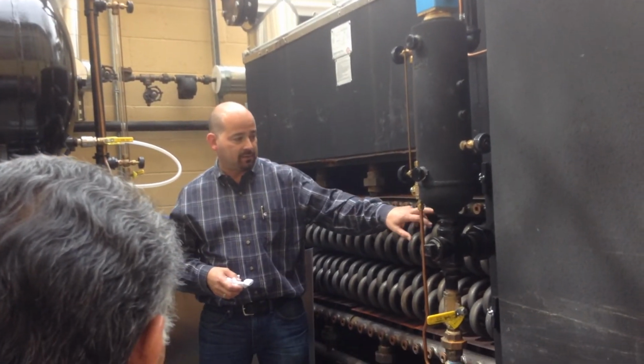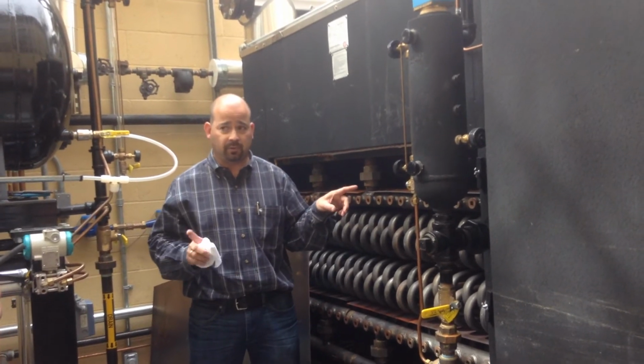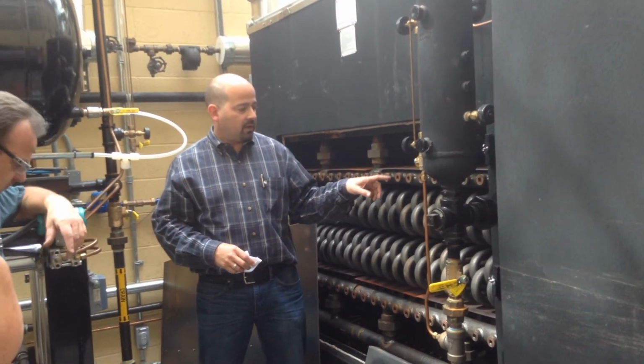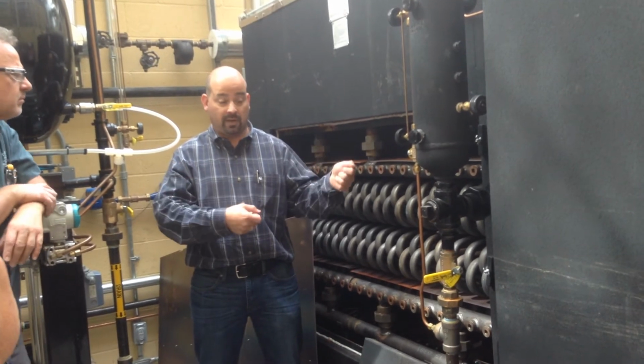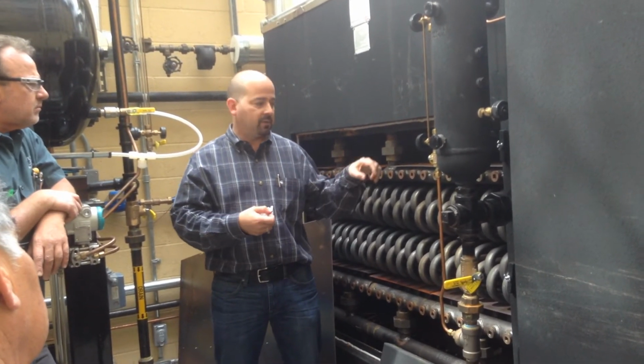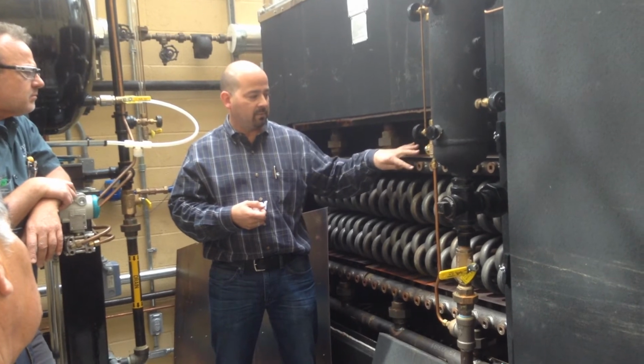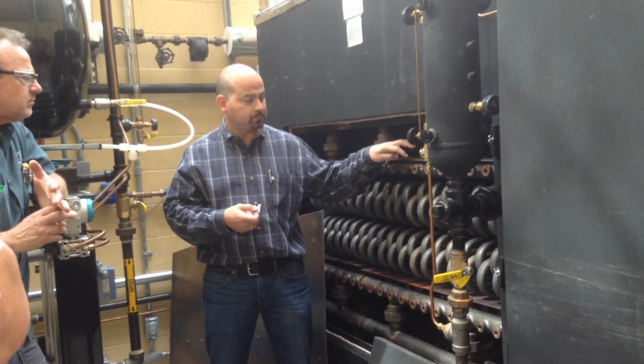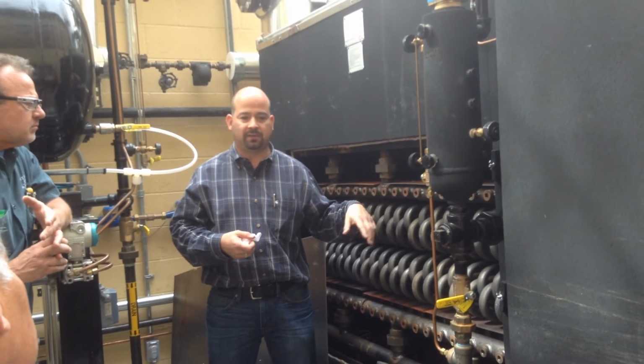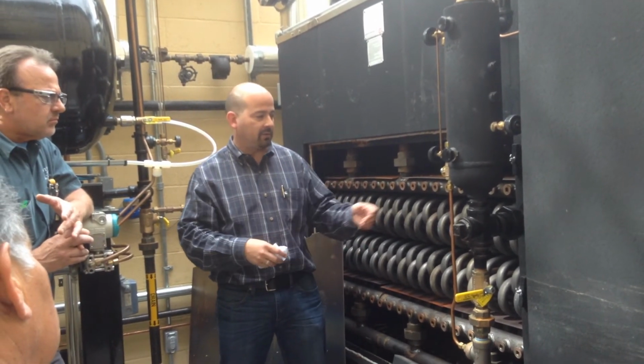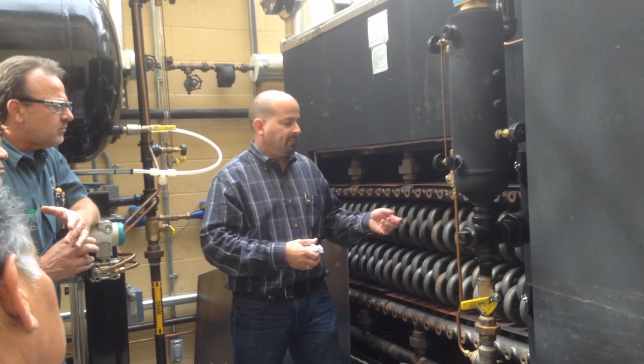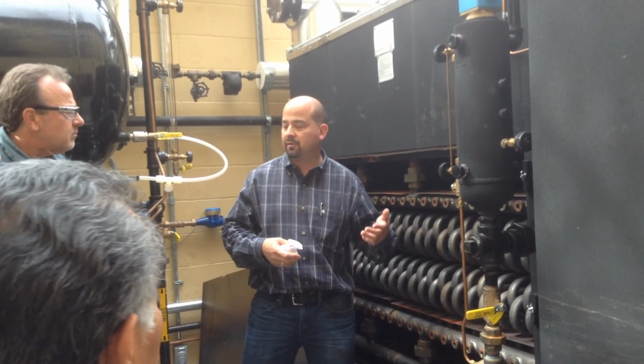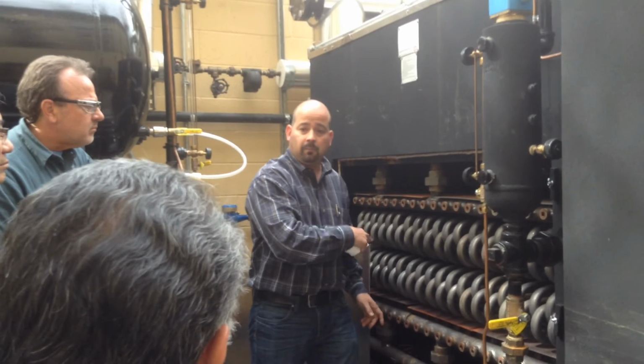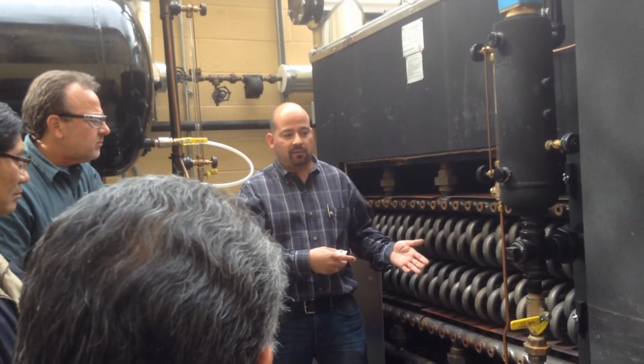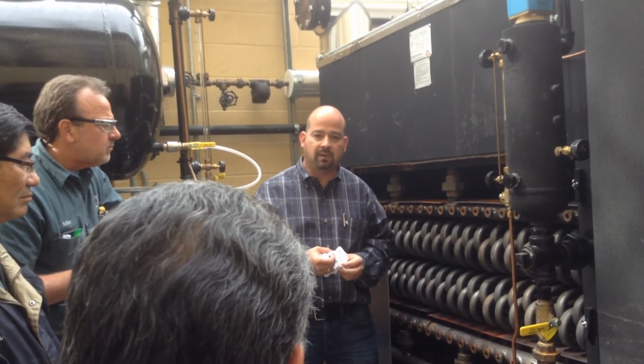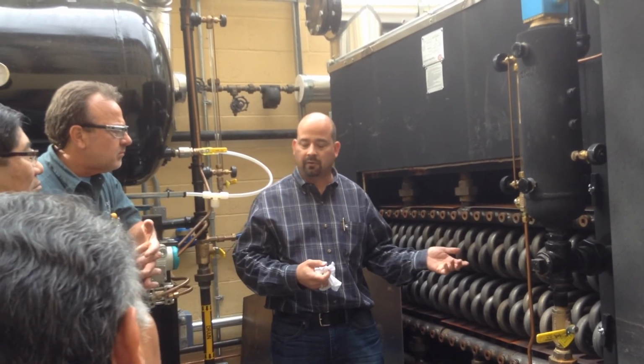These are inspection plugs. It's a straight thread, not tapered, and it's 3/4 inch, and the boiler came with a wrench, which is basically a breaker bar, and it came with extra copper O-rings, which are right here between the cap and the boiler itself, and plugs. So you should have at least 10, 20 extra ones already, but they're like $1.50 each or something like that. Anyway, when high pressure steam boilers, inspectors make us open up some that they want on every tube. Low pressure steam boilers, you're not subject to annual inspection by the state, so leave it up to you guys, however many you want to do.